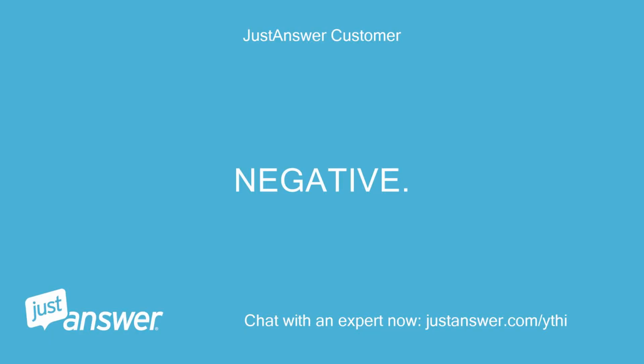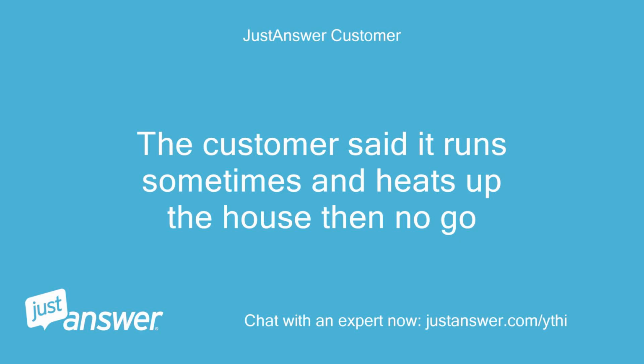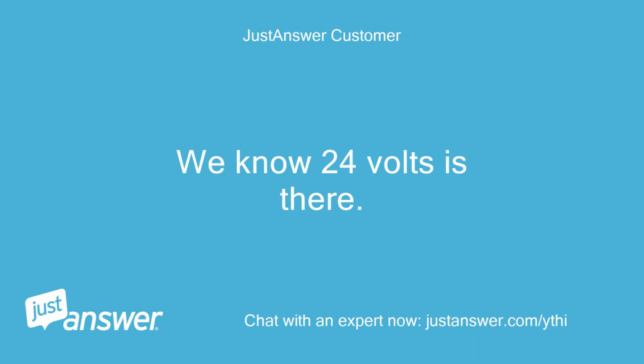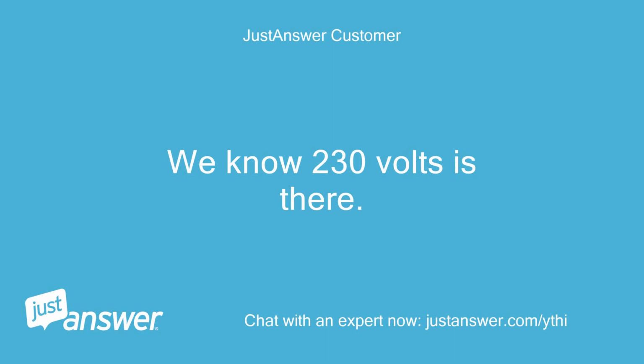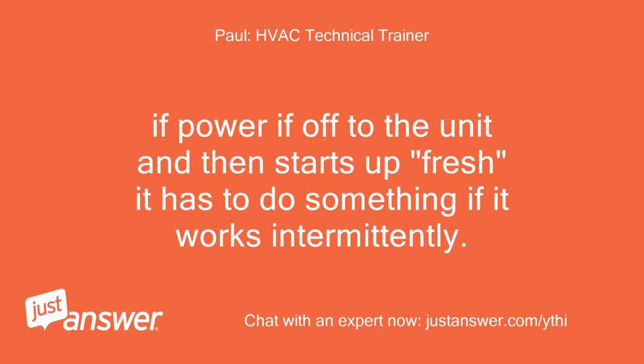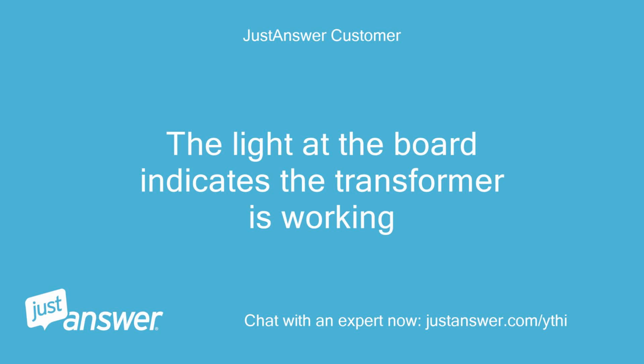Negative. Silent. The customer said it runs sometimes and heats up the house, then no go. We know 24 volts is there. We know 230 volts is there. If power is off to the unit and then starts up fresh, it has to do something if it works intermittently. The light on the board indicates the transformer is working.